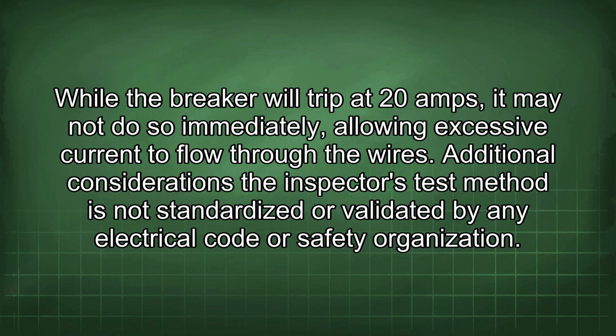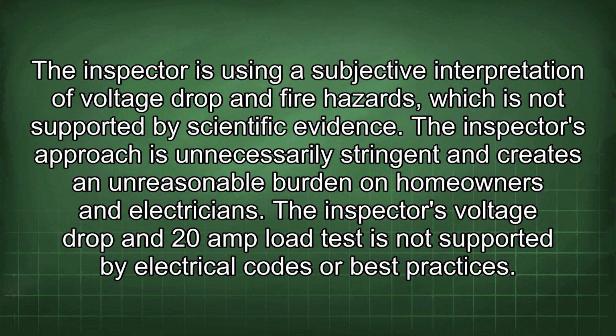the wires. Additional considerations. The inspector's test method is not standardized or validated by any electrical code or safety organization. The inspector is using a subjective interpretation of voltage drop and fire hazards, which is not supported by scientific evidence. The inspector's approach is unnecessarily stringent and creates an unreasonable burden on homeowners and electricians. The inspector's voltage drop and 20 amp load test is not supported by electrical codes or best practices.